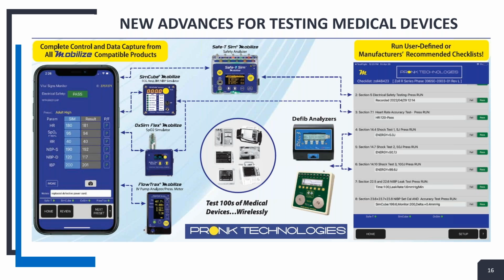What's the next test want us to do? Set to 30 plus or minus 1.5. 30 milliamps of current for pacing, and a pass is plus or minus 1.5. And what's the pulses per minute it wants? 40 plus or minus 2. So we need to set the pulses per minute to 40. Once we have it set up here, of course, we still need the technician to set it up. Go ahead and run it. And it's running, so go ahead and hit run.